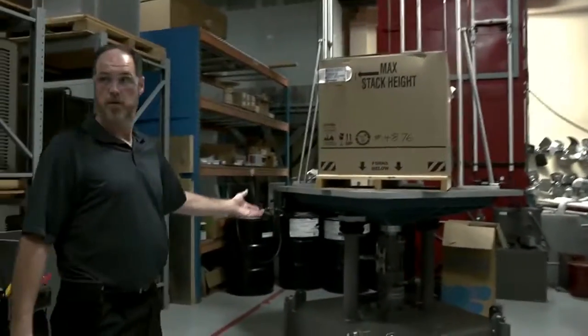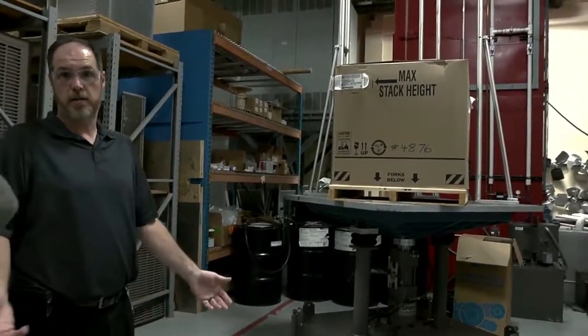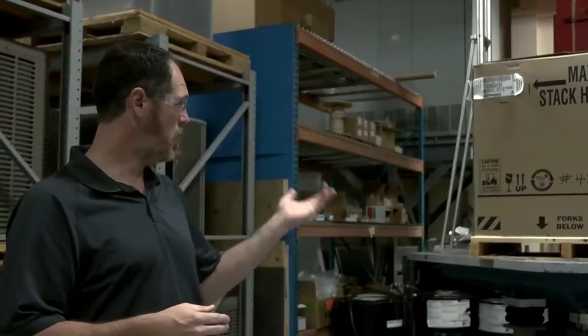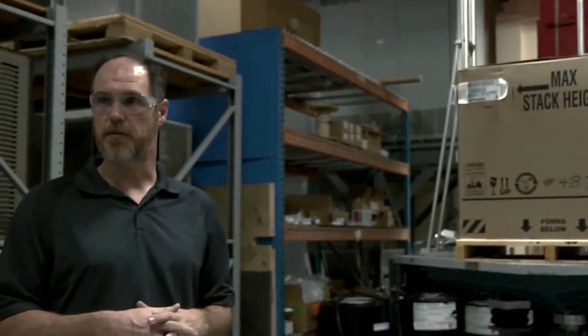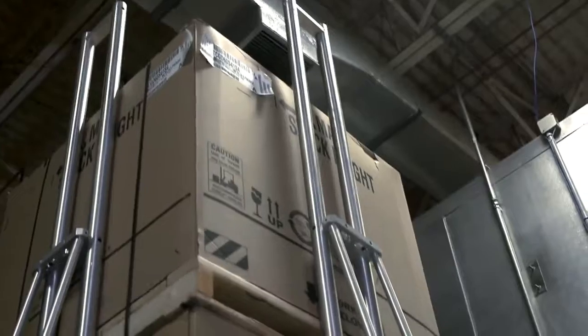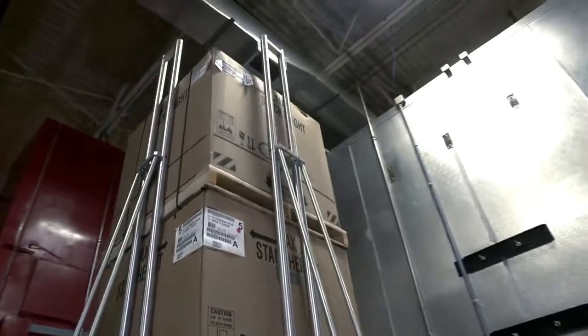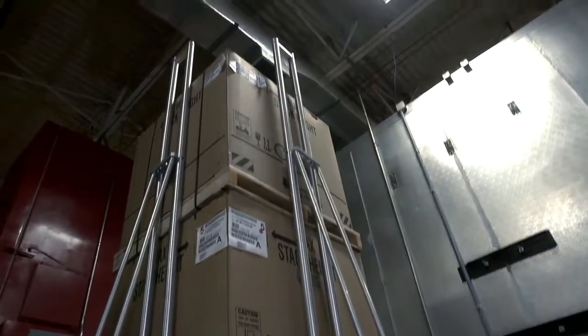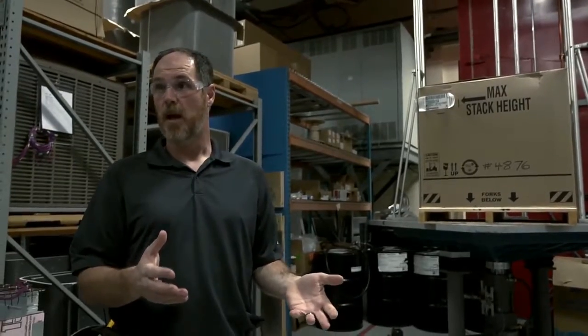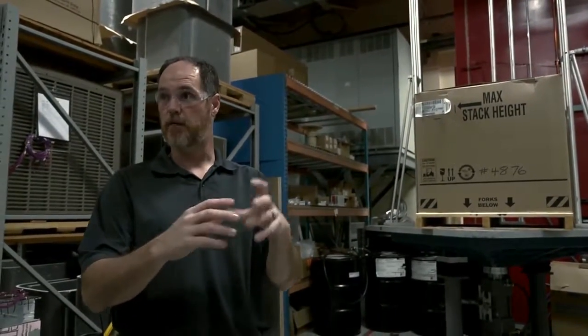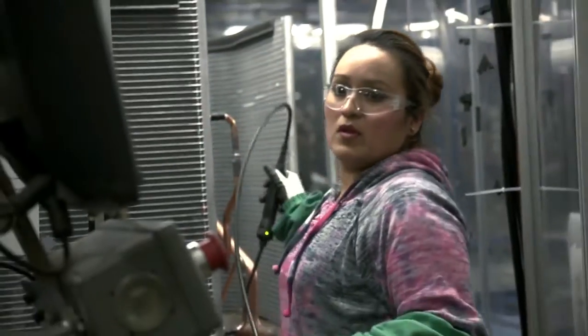Transit tester. So really, you can call it a shake table. And the equipment will bounce an inch or so off the table. If we're doing a new product and we're trying to design it based on shipping, test it till it fails and figure out what failed. And then that gives us a weak point that we can focus on and we can redesign and we can try and make sure it withstands what we've put it through.